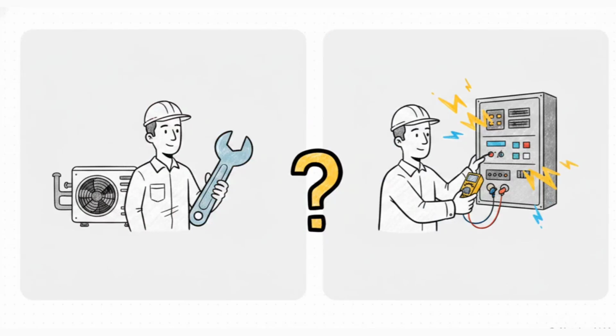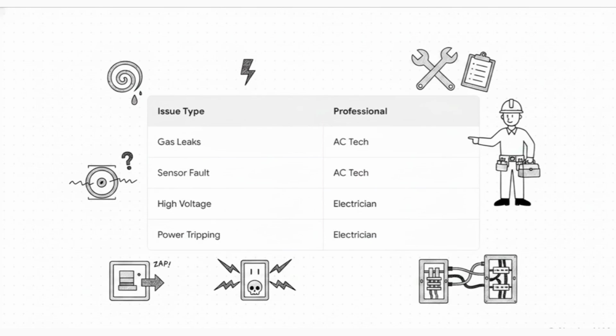And speaking of the system tripping, this brings us to our final major diagnostic distinction. When the power cuts out every single time you turn the AC on, who do you actually call? Do you need an AC technician or do you need an electrician? Let's clearly delineate these 2 roles so you don't waste your time or your money. If you're dealing with gas leaks, sensor issues, or failing internal parts, you call the AC tech. However, if your AC trips the main breaker the very moment you turn it on, and you discover that the current or voltage coming from your house's main switchboard exceeds the AC safety specifications, an AC technician cannot help you there. That's an electrical supply issue. You need an electrician to fix the switchboard and ensure stable voltage is actually reaching the unit.